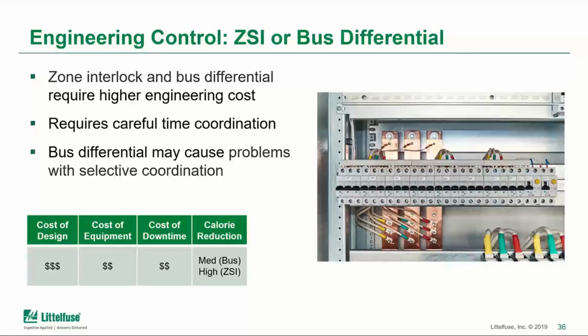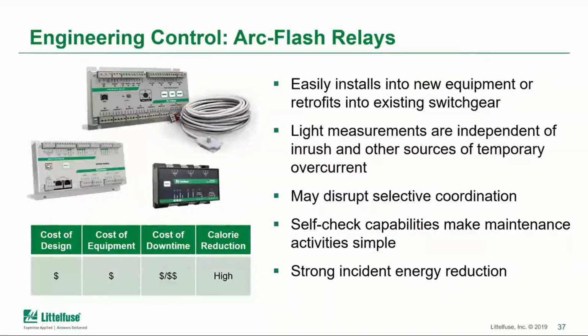And the time frame to do that could be multiple days once you're trying to put that all into your system. And finally, under the calorie reduction, both of these methods are quite effective, so listed on the medium and high scale there. Another engineering control that is mentioned is using arc flash protection relays.